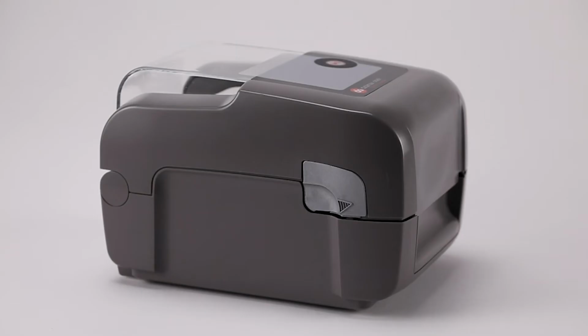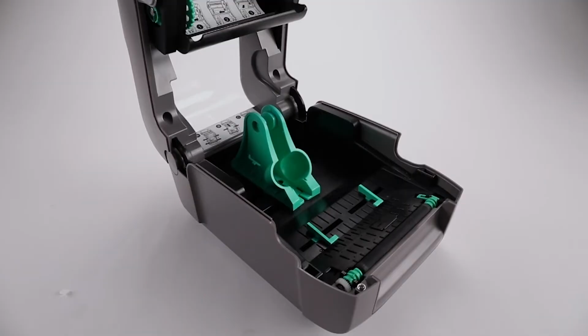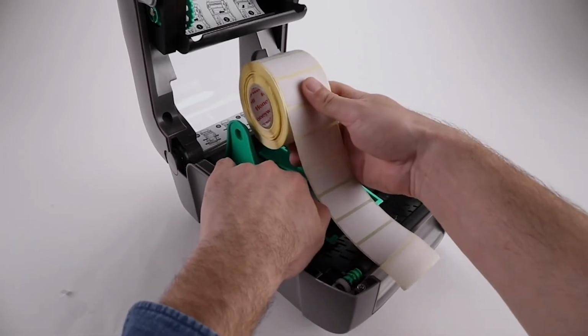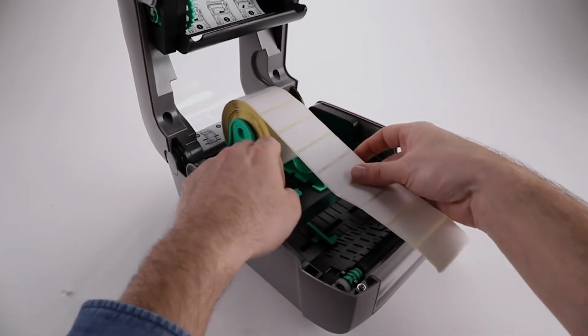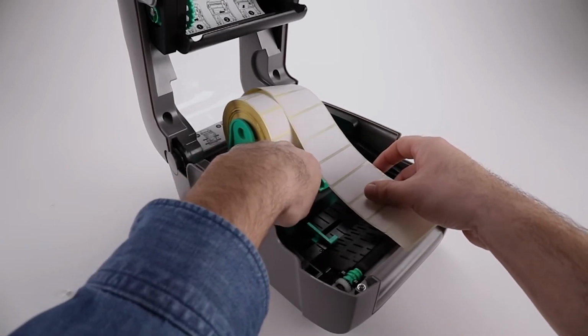If your E-Class Mark III displays a red fault light after replacing any media supplies, ribbon and labels, follow these steps. Mechanical troubleshooting: make sure the supplies are correctly installed. Media hangers should be holding the roll of labels on both sides, and the media guides are adjusted so they are lightly touching the edge of the media.